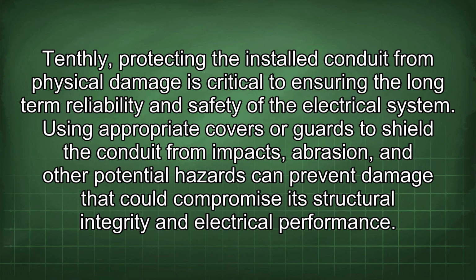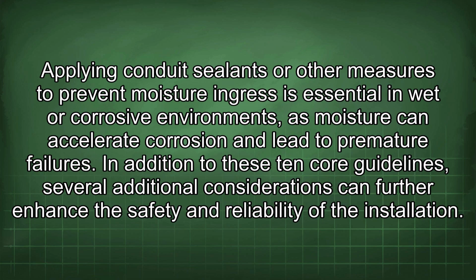Using appropriate covers or guards to shield the conduit from impacts, abrasion, and other potential hazards can prevent damage that could compromise its structural integrity and electrical performance. Applying conduit sealants or other measures to prevent moisture ingress is essential in wet or corrosive environments, as moisture can accelerate corrosion and lead to premature failures.